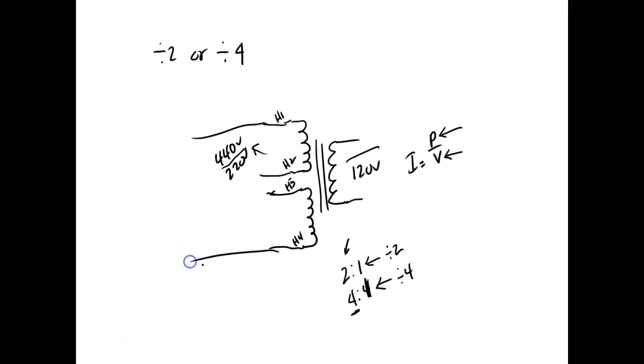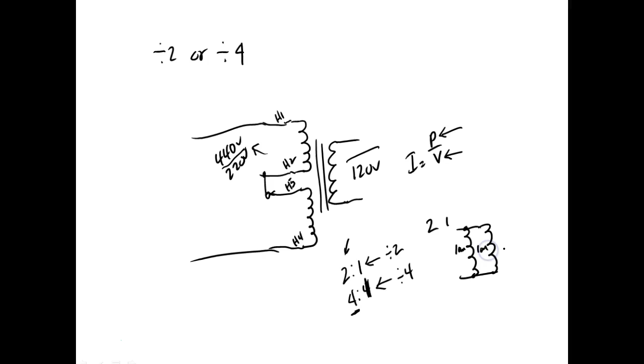So that means we need to connect H2 to H3. Now look, all the turns - we get more turns, but the current is lower, right? Now if I hook something in parallel, the current is shared between the 2 windings. So if this is 1 amp and this is 2 amps, this guy would conduct 1 amp, and that would conduct 1 amp. So if I want a divide by 2, we hook them in parallel.